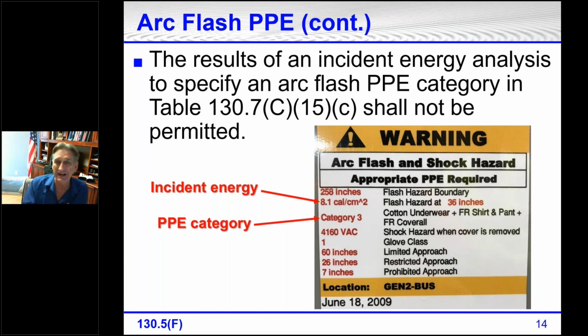if it didn't have category 3 on the label, then whoever's working in front of this equipment, even racking in, racking out the breaker, all they would have had to wear was arc rated clothing, hard hat, face shield, everything rated up to 8.1 calories. 8.1 or above. Because it went above 8, the category that was put on there was 3.